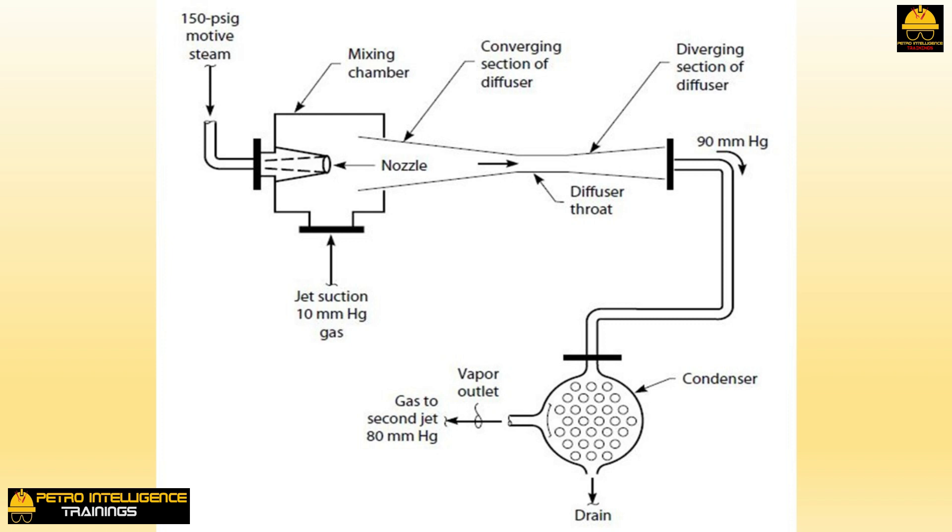The steam is going to a condenser, which will condense the steam at a low temperature and low pressure. The steam accelerates toward the cold surface of the condenser tubes, where its large volume disappears as steam turns to water. The motive steam accelerates to such a great velocity that it can greatly exceed the speed of sound — sonic velocity. This tremendous increase in velocity represents a tremendous increase in kinetic energy, sourced from the temperature and pressure of the steam.